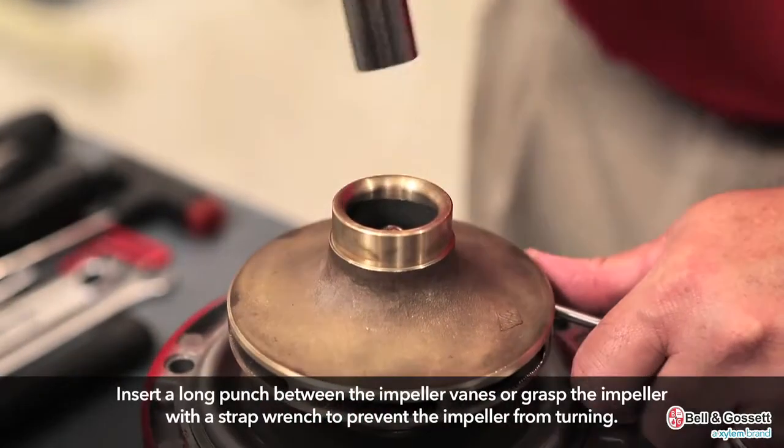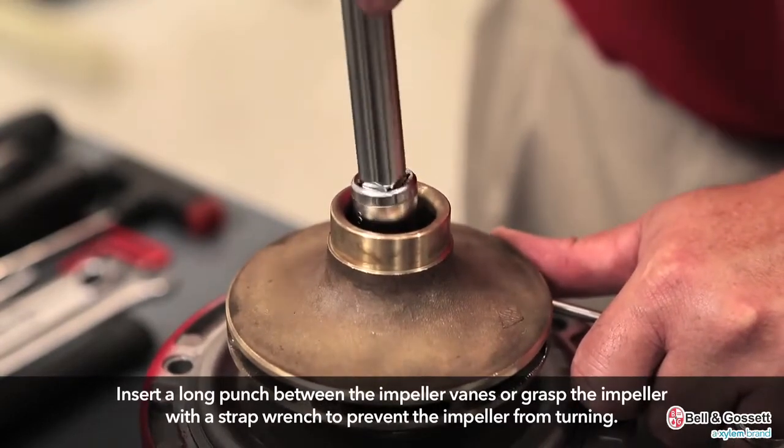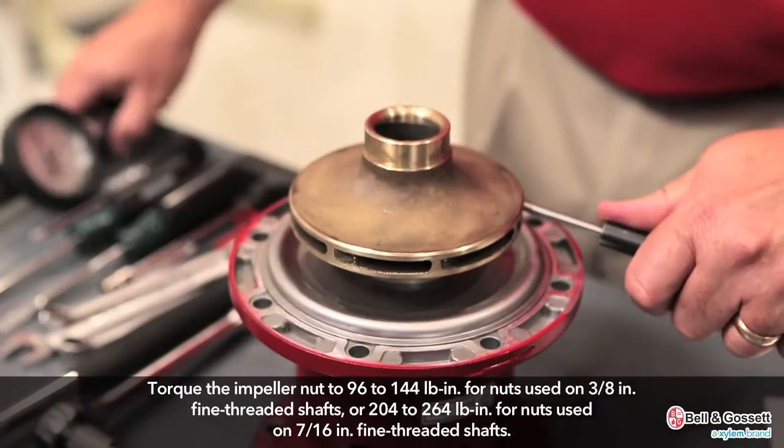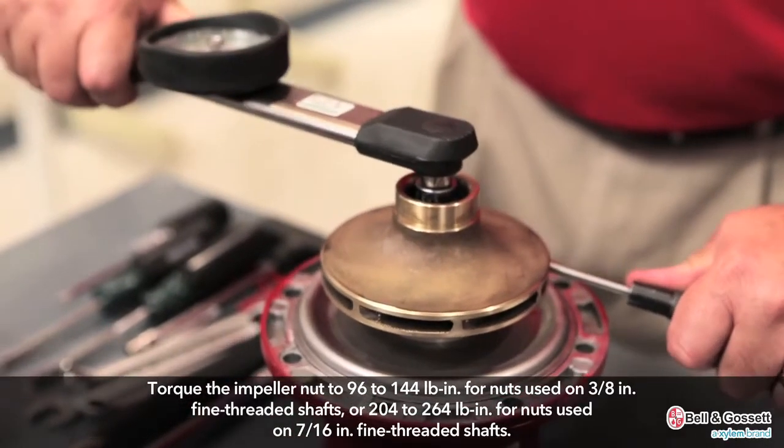Insert a long punch between the impeller vanes or grasp the impeller with a strap wrench to prevent the impeller from turning. Torque the impeller nut to 96 to 144 pound inches for nuts used on 3/8 inch fine threaded shafts.